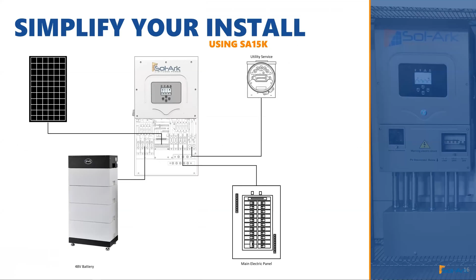A key goal of ours is to simplify that install. A couple slides ago I talked about the integrated transfer switch in all of our inverters, but I want to highlight our Sol-Ark 15K with this slide. That inverter comes with a 200 amp integrated grid connection, which enables you to really cut down on the amount of equipment external to the Sol-Ark required to facilitate whole home backup using this inverter.